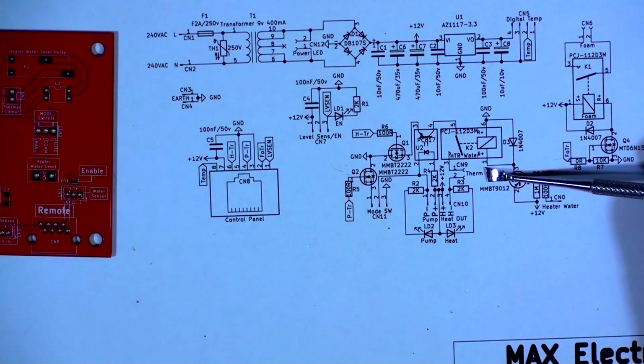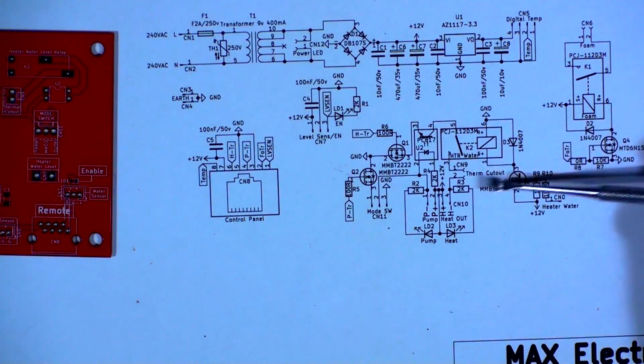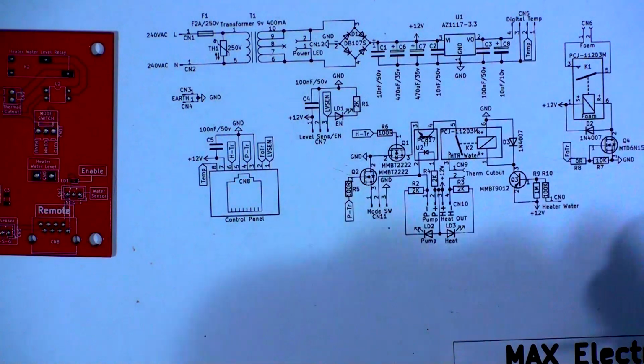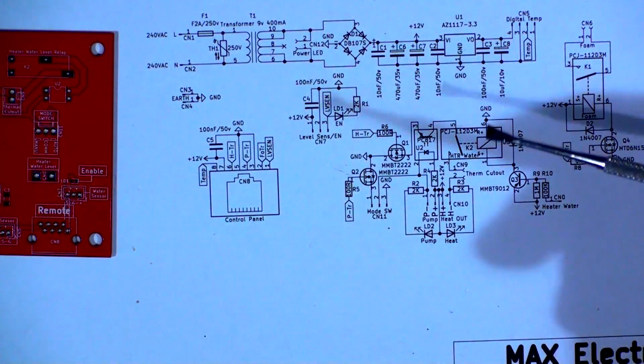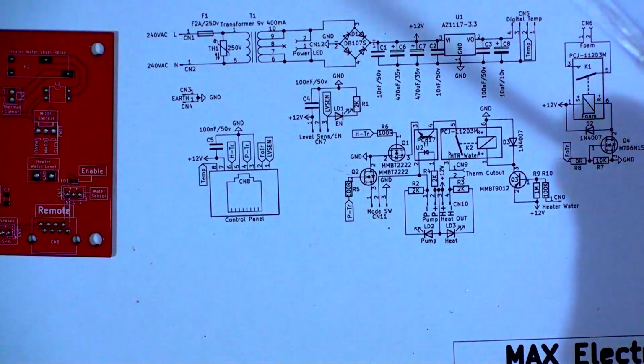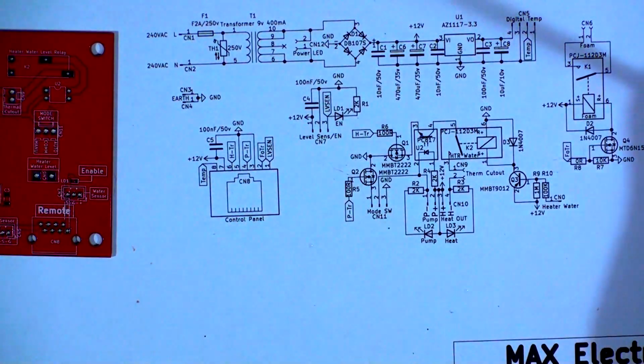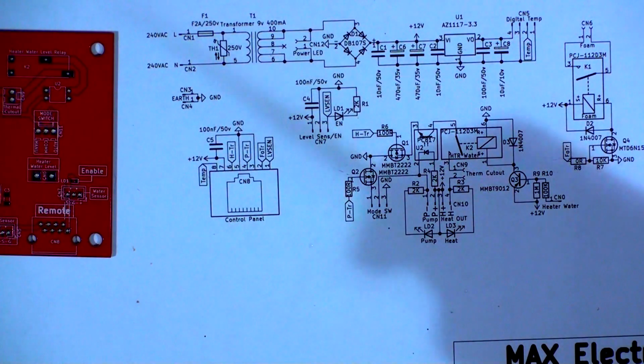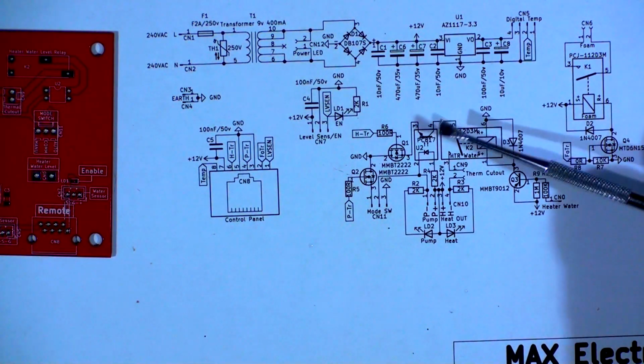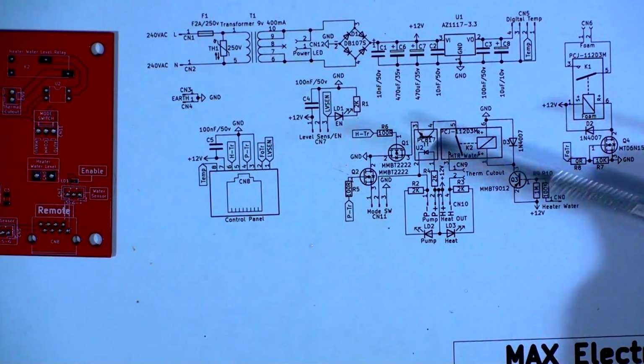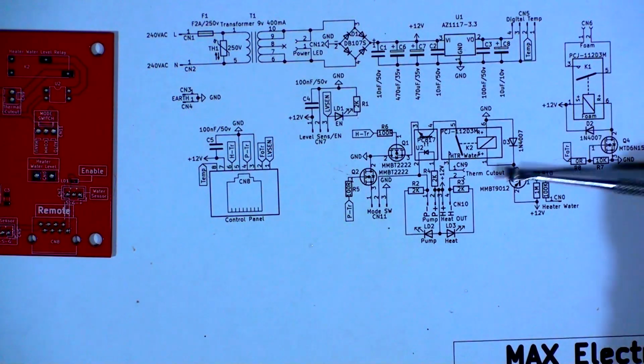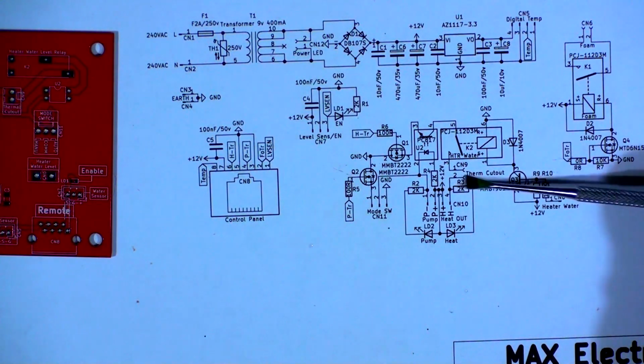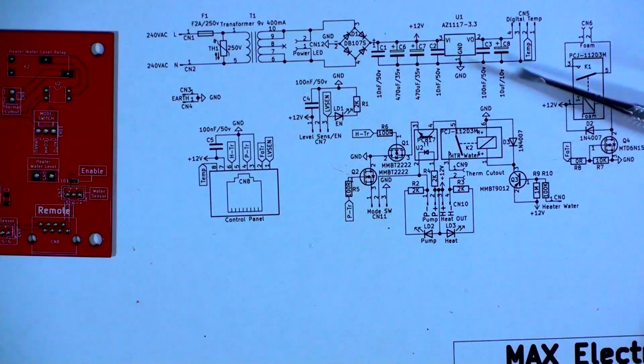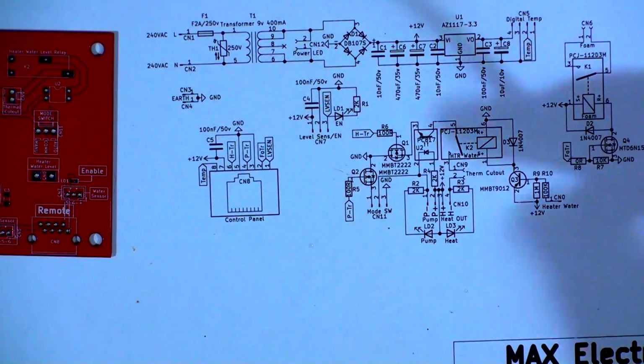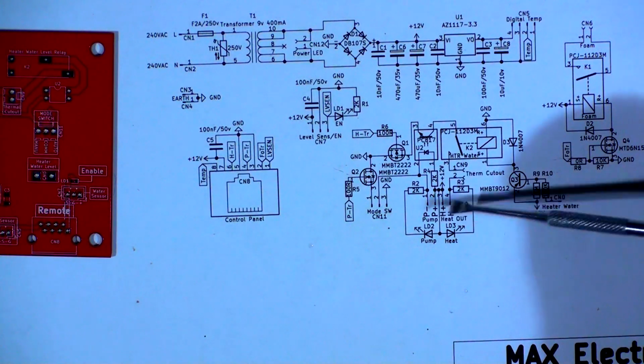And usually what I do with this thermal cutout, because there's enough safeties already, I usually put a thermostat, an old school thermostat, the one that's got a little tube and it's mechanical, and you set it to maximum temperature, let's say 42 degrees or something, so it can't go further than 42. If something goes wrong, say the controller freezes, the relay breaks down, I don't know, the whole thing just breaks, you still got a last thermal cutout that it will heat up to 42, and then that thermostat will click off, and then it goes to the heating relay.